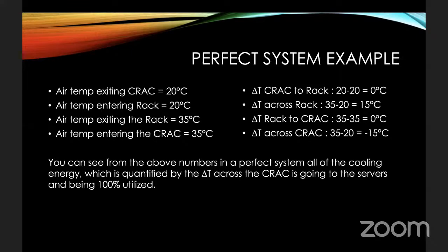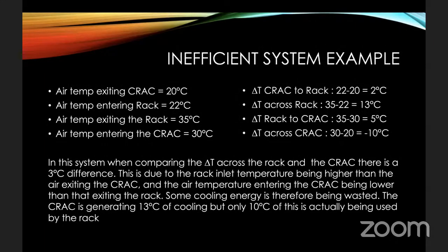100% of the cooling energy coming out of our CRAC is being consumed by the servers and carried back to the CRAC and cooled down and recirculating again. So this is an ideal system, and this is what you want to aim for. If you can achieve this, then 100% of your cooling energy is being used by the servers. If your numbers do not match this, then your system is not perfect and it is not as efficient as it could be. So here is an example of an inefficient system.